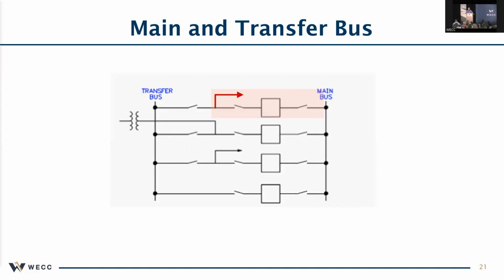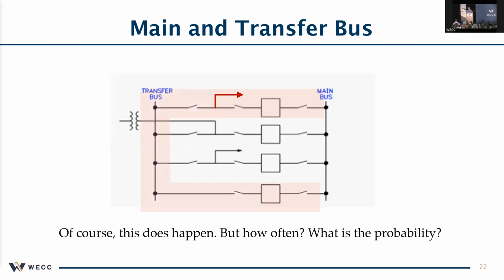And then most auditors in WECC, if they saw this arrangement, would ask, what about this transfer bus? What if you're powering that line from the transfer bus? So in this case, you give them the information on these facility elements. That's fine. You can still rate it based on the main bus, but they just want to be aware. This is the kind of thing that would be built into a procedure for your operators when they're transferring around. Is there no concern over the flow going through that transfer breaker? What if you're having to provide 2 circuits instead of 1? So that rating information needs to be there somewhere, and the auditors will explore that and ask about that rating.